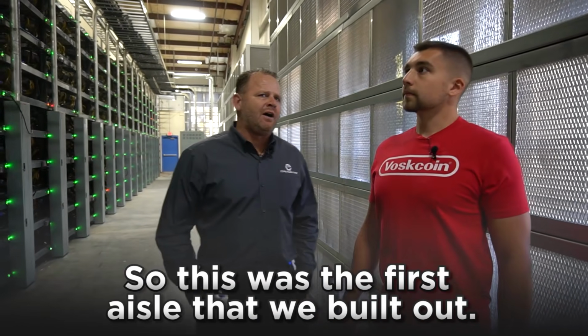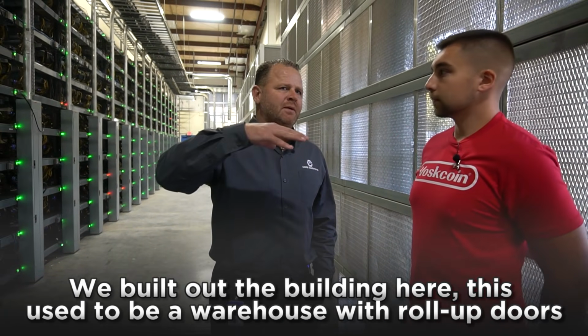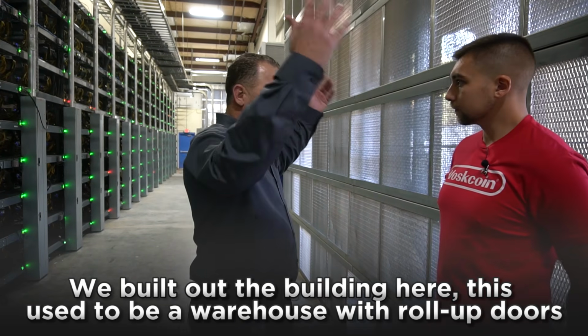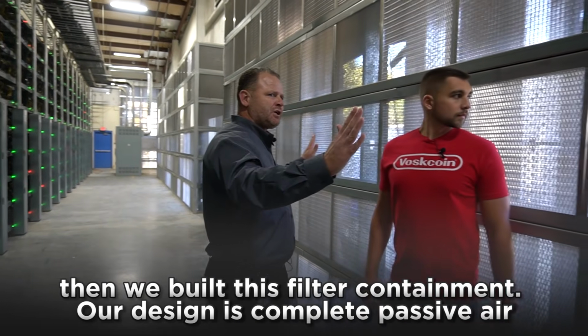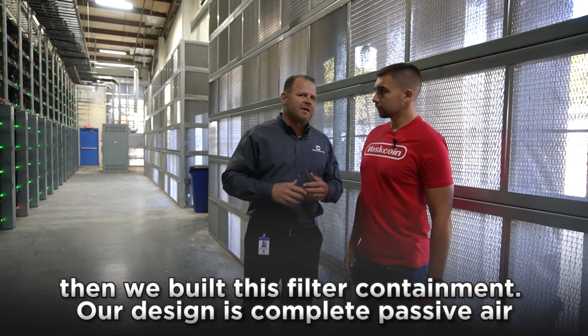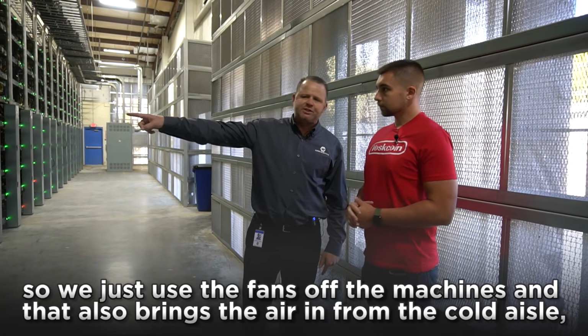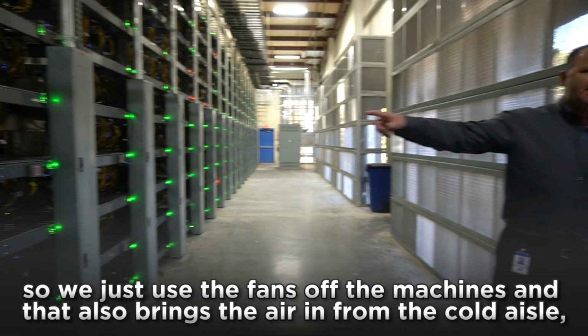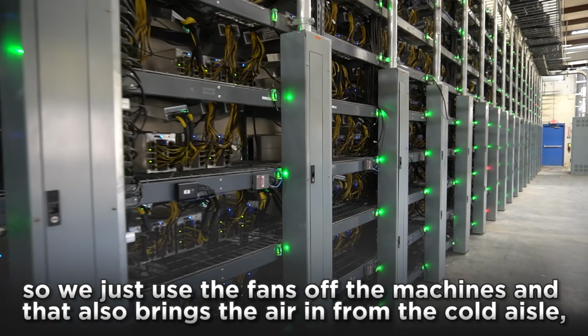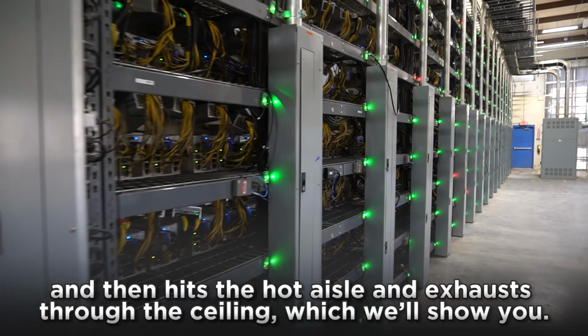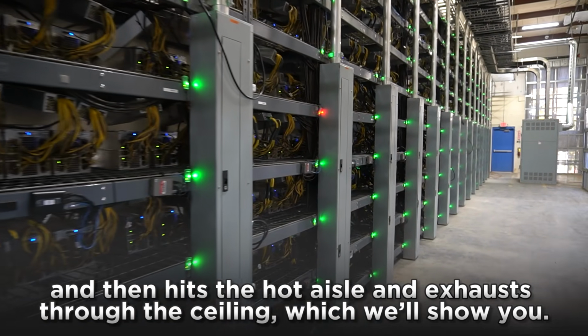This was the first aisle that we built out. We built out the building here. This used to be a warehouse with roll-up doors, and we built this filter containment. Our design is complete passive air, so we just use the fans off the machines, and that's what brings the air in from the cold aisle, then hits the hot aisles and exhausts through the ceiling, which we'll show you.